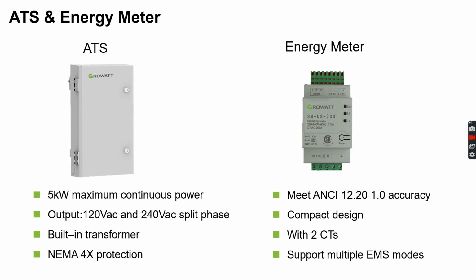Growatt's ATS and Energy Meter are both needed if customers want to add a backup solution for their home or backup loads. The ATS, which stands for Auto Transfer Switch, will have a maximum continuous power of 5 kilowatts and be able to output both 120 volts or 240 volts split phase. The Energy Meter is needed to monitor power flow to home consumption and backfeed with higher accuracy and will support 2 current transformers to monitor the power flow through the main panel. This Energy Meter will support multiple EMS modes such as self-consumption, time of use, and off-grid modes.